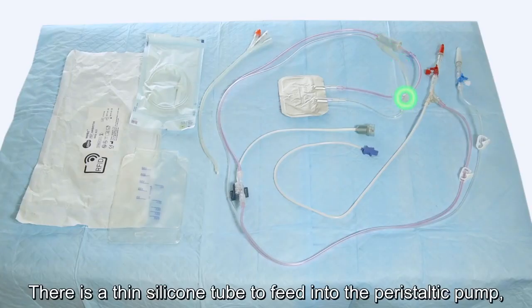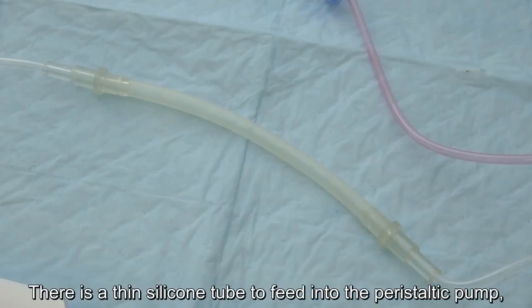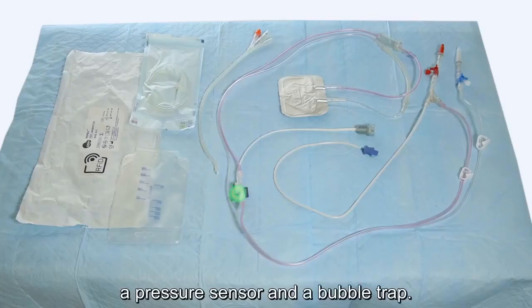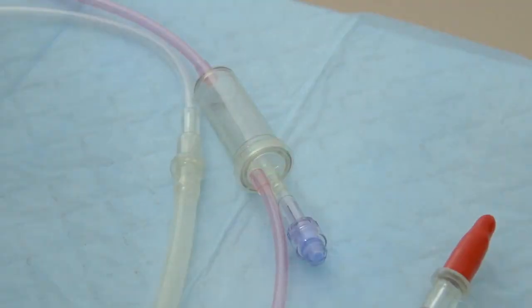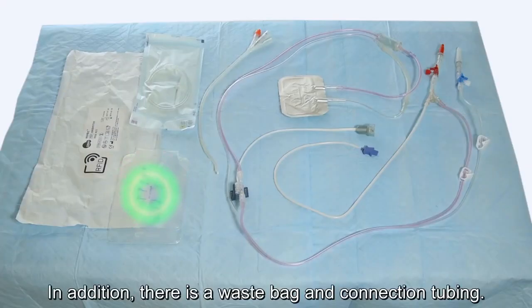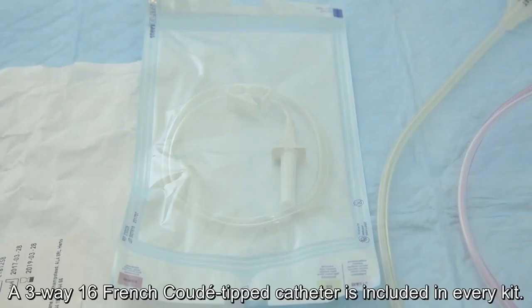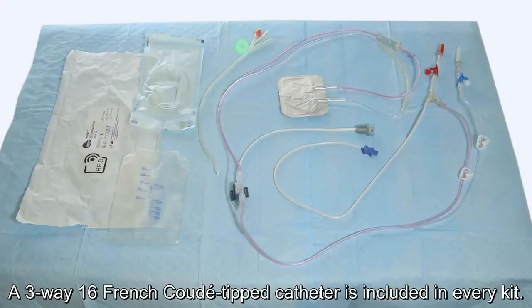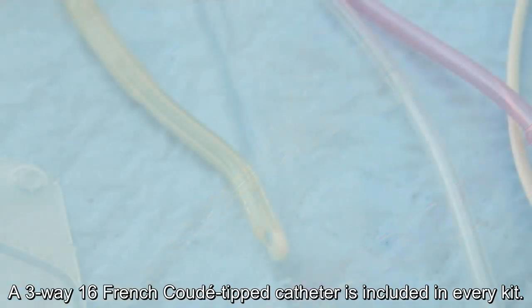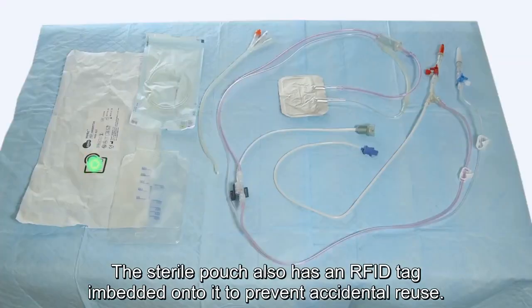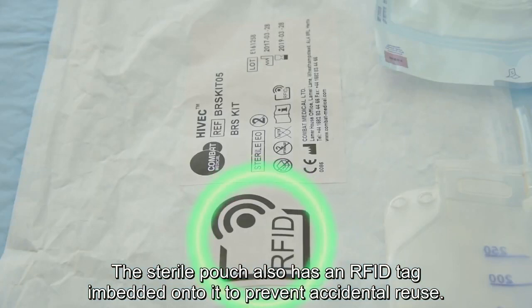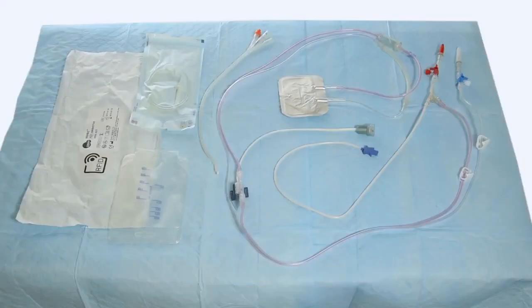There is a thin silicone tube to feed into the peristaltic pump, a pressure sensor and a bubble trap. In addition, there is a waste bag and connection tubing. A 3-way 16 French Coude tipped catheter is included in every kit. The sterile pouch also has an RFID tag embedded onto it to prevent accidental reuse.